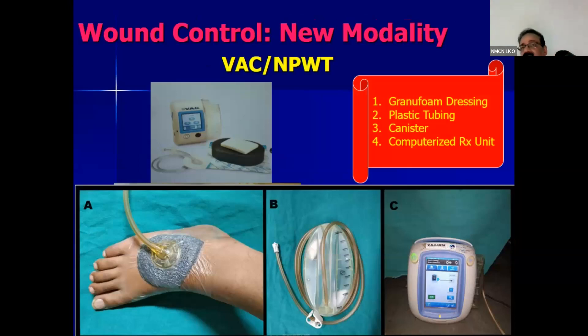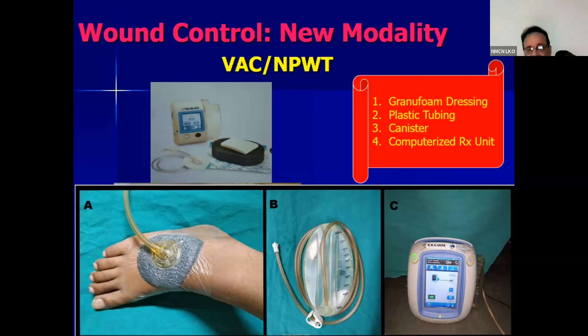Negative pressure wound therapy or VAC is now not a new modality — it has become a standard of care for chronic ulcer healing, particularly diabetic foot ulcers. In this technique, foam is put over the wound and through a tubing it is connected to a computerized therapy unit with a canister. Whatever discharge comes out is aspirated into the canister, and you can adjust the negative pressure using this computerized unit.